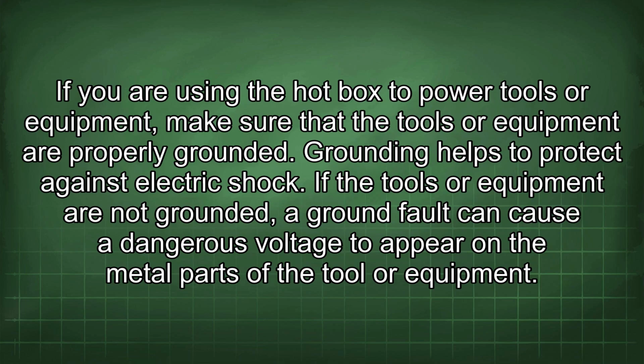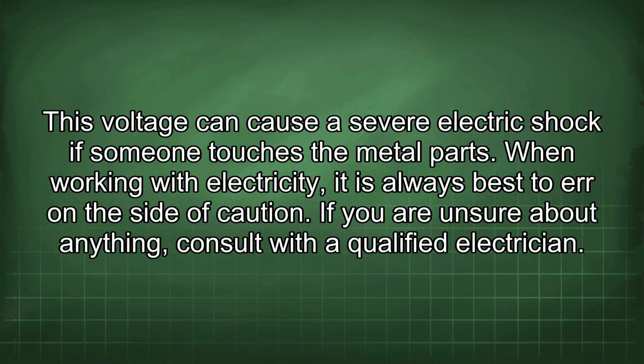If you are using the hotbox to power tools or equipment, make sure that the tools or equipment are properly grounded. Grounding helps to protect against electric shock. If the tools or equipment are not grounded, a ground fault can cause a dangerous voltage to appear on the metal parts of the tool or equipment. This voltage can cause a severe electric shock if someone touches the metal parts. When working with electricity, it is always best to err on the side of caution. If you are unsure about anything, consult with a qualified electrician.